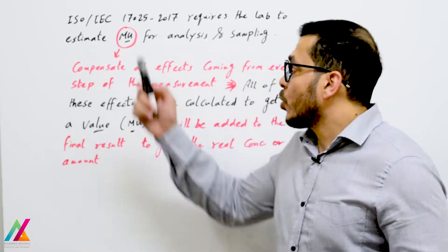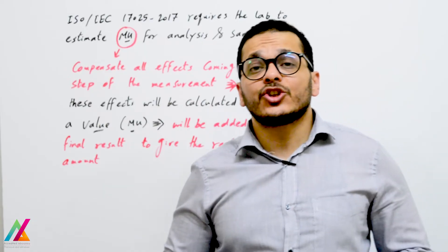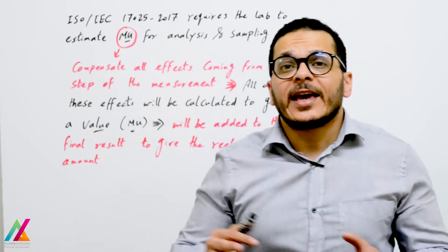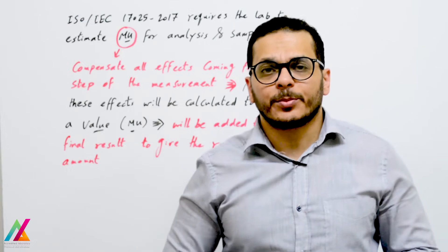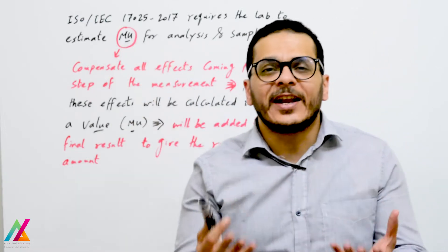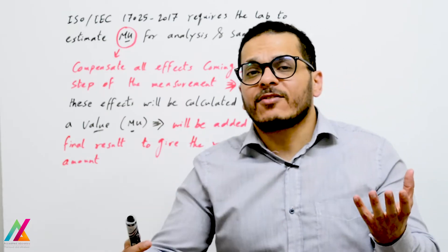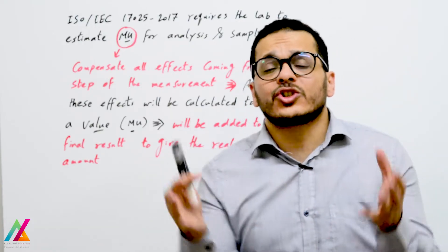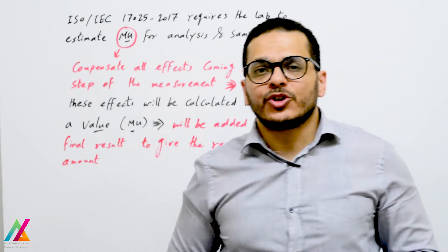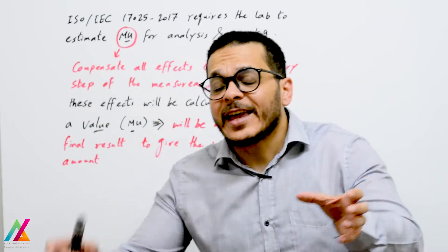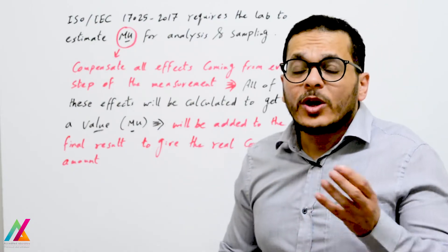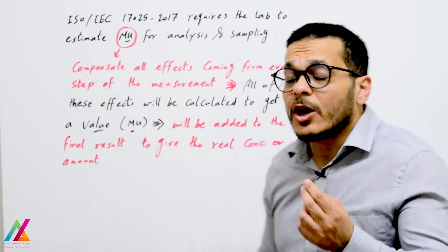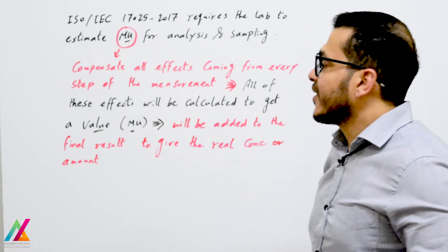Whether for microbiology, chemistry, or any other type of analysis, ISO/IEC 17025:2017 requires the lab to estimate measurement uncertainty for analysis and for sampling — for the whole measurement process. Measurement uncertainty is a value that is added to the final result for each sample to compensate for all sources of errors coming from every step of the measurement process, from sampling up to giving the result.